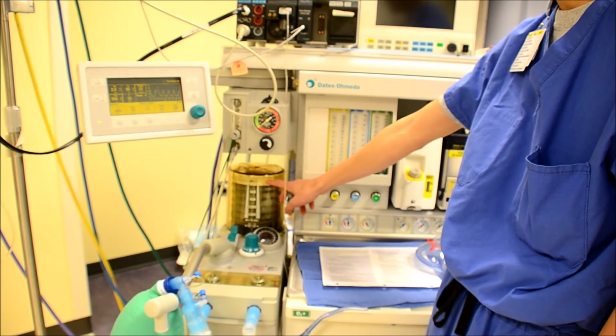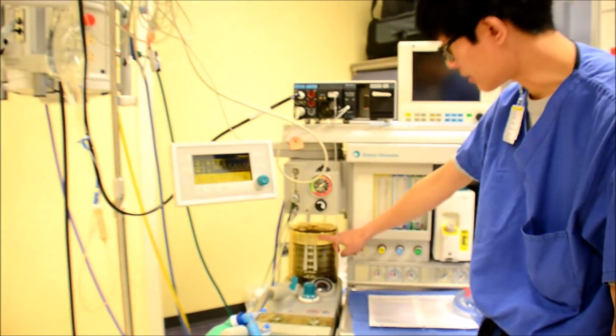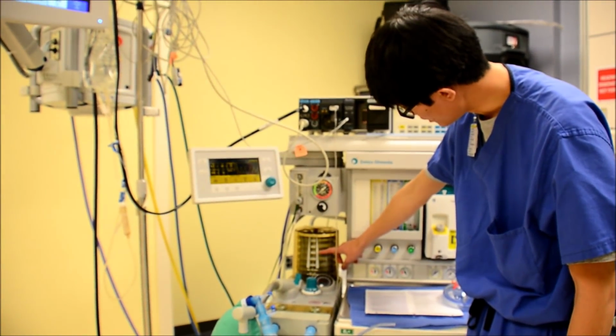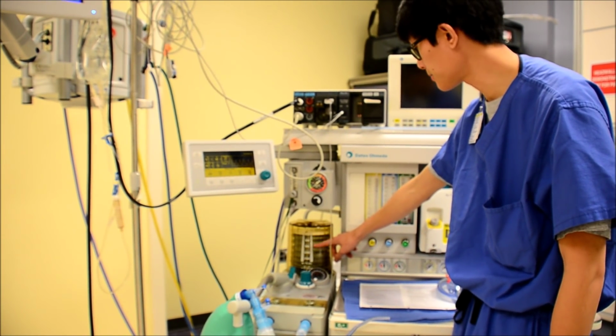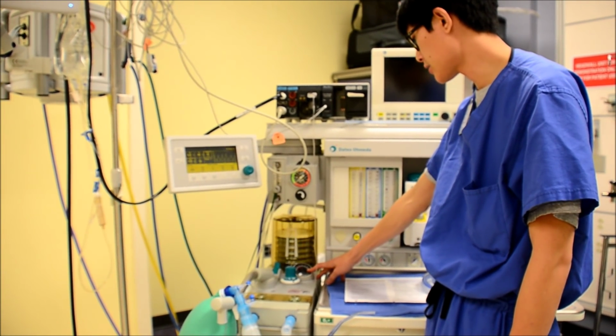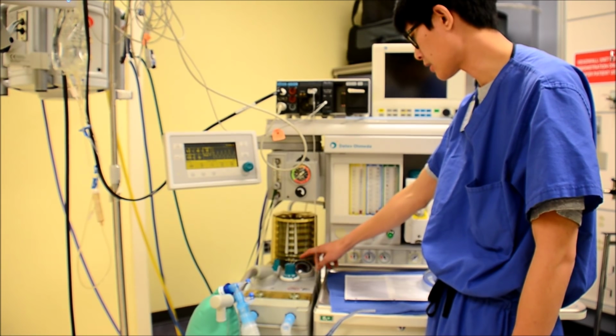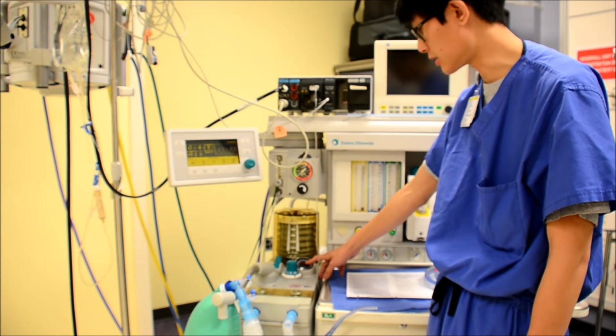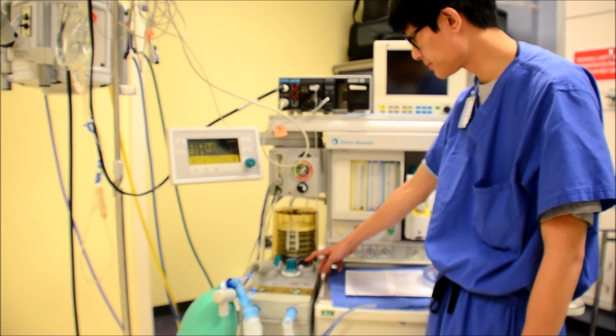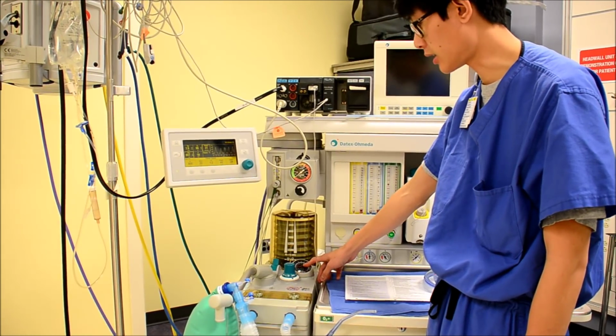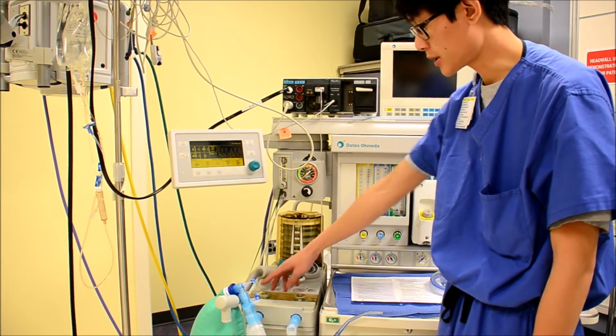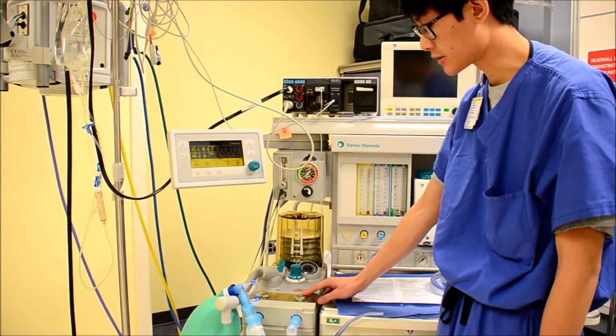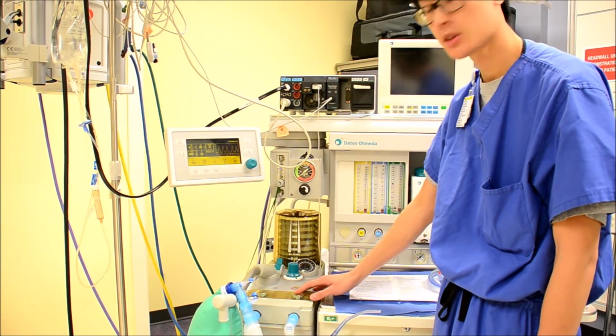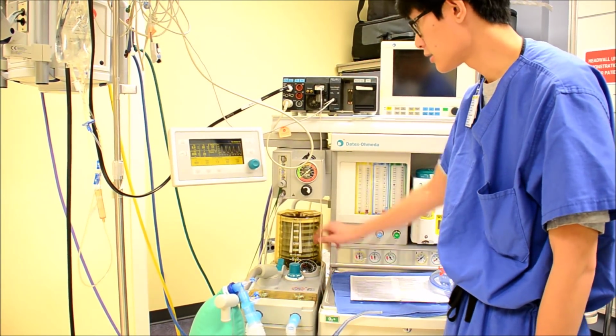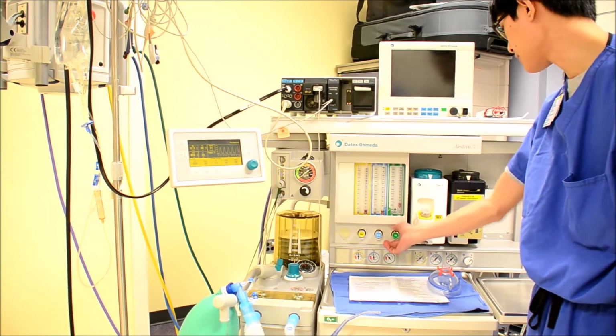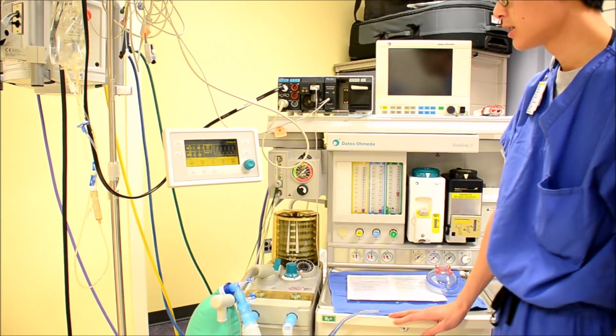Make sure the volume that you've set on the monitor is about where the bellows is dropping down to, which is 800. We'll check our pressure gauge to make sure that the needle drops all the way back down to 0 centimeters of water with each breath, to make sure we're not auto-stacking breaths. And we'll make sure the inspiratory and expiratory valves are not sticking and they're free flowing. So once we do that, we'll increase our flow to 5 liters a minute and check the same thing.